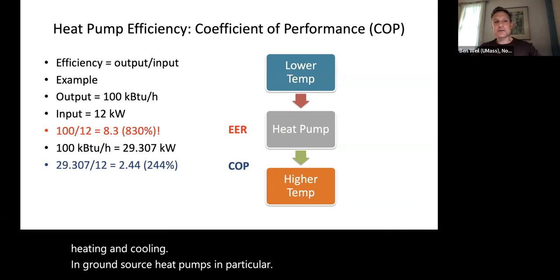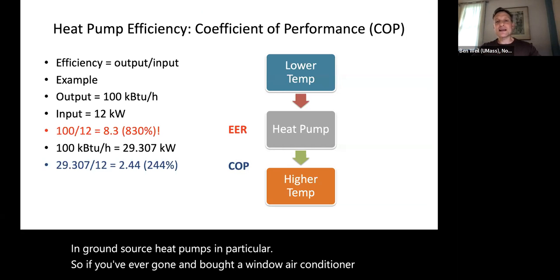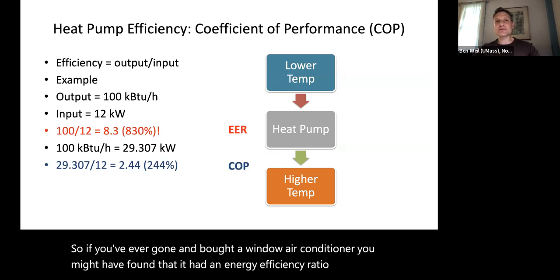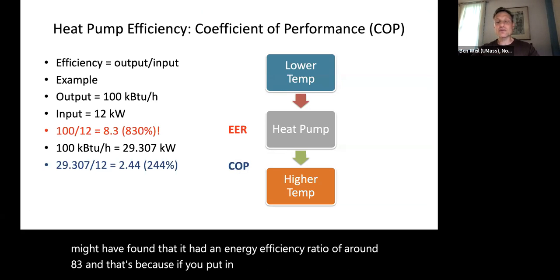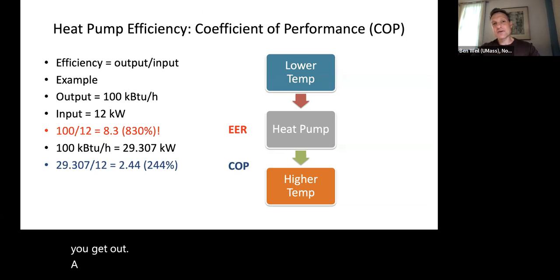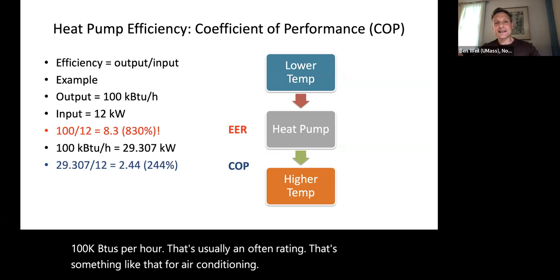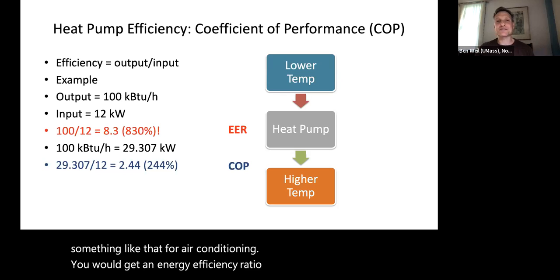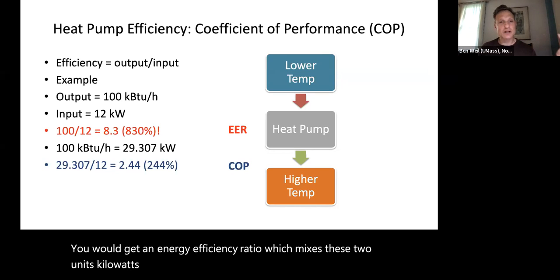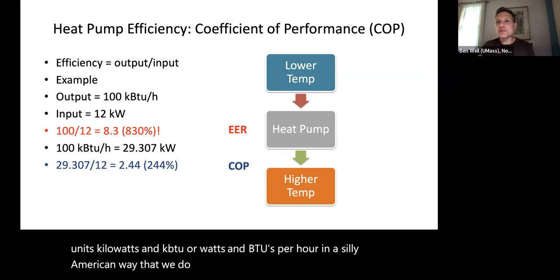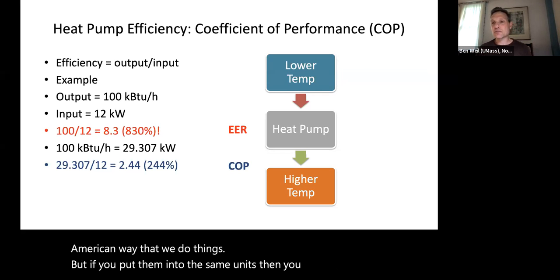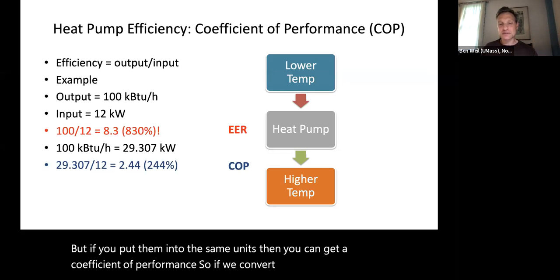So if you've ever bought a window air conditioner, you might have found that it had an energy efficiency ratio of around 8.3. And that's because if you put in 12 kilowatts of energy and you get out 100 kBTUs per hour, that's often a rating for air conditioning. You would get an energy efficiency ratio which mixes these two units, kilowatts and kBTUH, or watts and BTUs per hour, in a silly American way that we do things. But if you put them into the same units, then you can get a coefficient of performance. So if we can convert our BTU per hour to watts, then we can get a coefficient of performance.